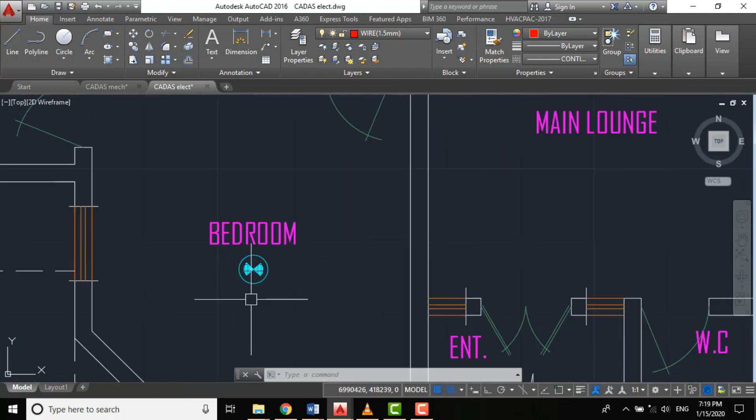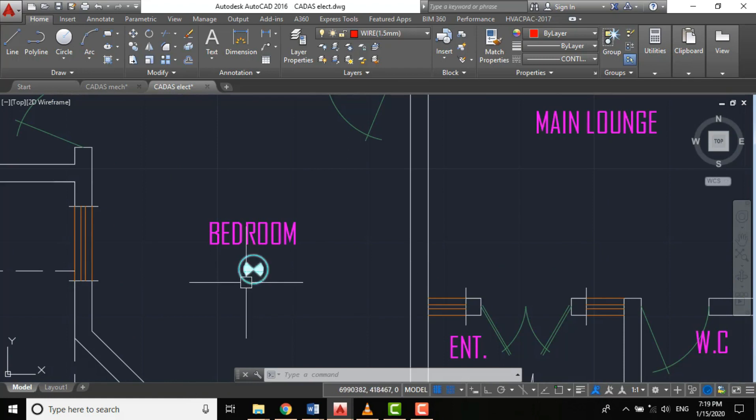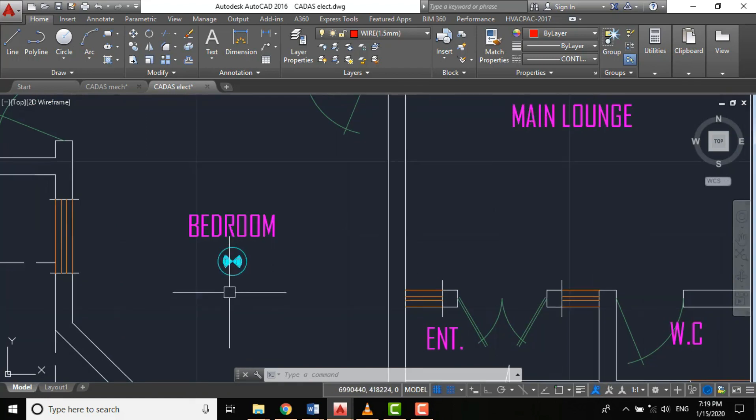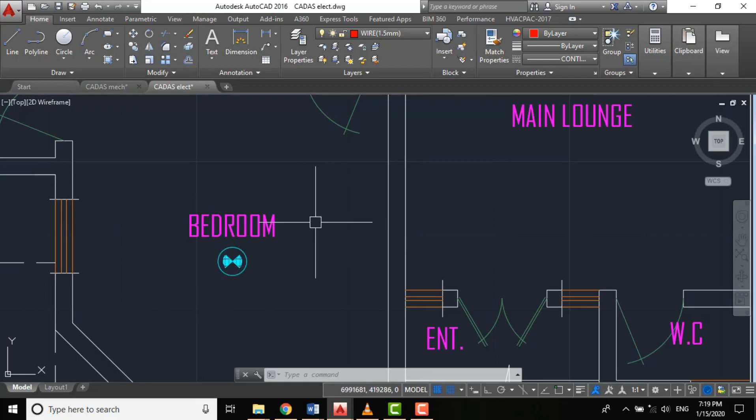For a smoke detector, the coverage diameter is 10 meters, which means the spacing between two smoke detectors is 10 meters.